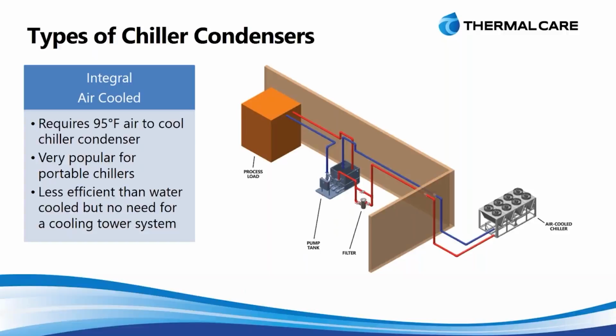Those air to refrigerant heat exchangers act a lot like a radiator in your car. They're using fans with forced air to remove the heat. With those, you have additional motors running, so you have additional electrical draw, and so the units aren't quite as efficient as, say, a water-cooled, but they have a lot of other benefits, like you don't need that cooling tower infrastructure there. You don't need any of the treatments and the chemicals and the consumption that a cooling tower system has either. So there are a lot of benefits. These a lot of times could be very much a plug and play setup, especially if that pump and tank is incorporated into the chiller itself. It's a packaged unit. You plumb it up, you put power to it, and it's ready to go. So that's one of the very nice things about these units.